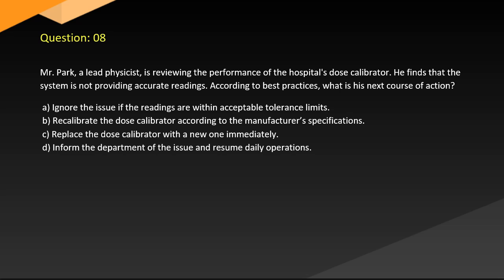A. Ignore the issue if the readings are within acceptable tolerance limits. B. Recalibrate the dose calibrator according to the manufacturer's specifications. C. Replace the dose calibrator with a new one immediately. D. Inform the department of the issue and resume daily operations.